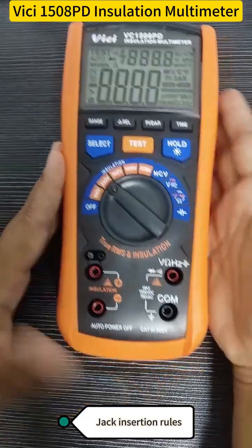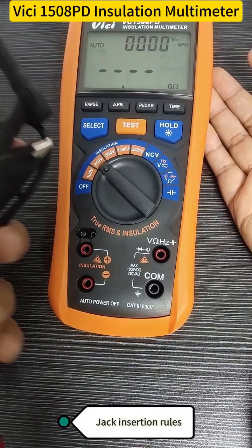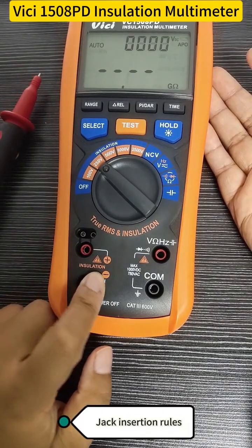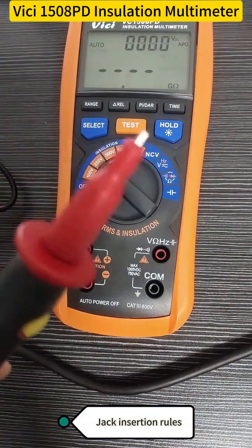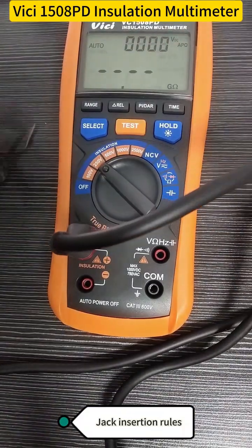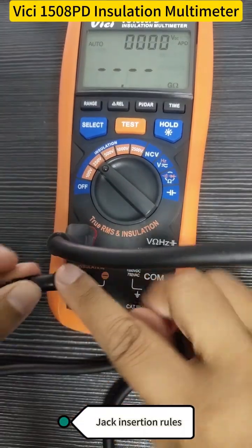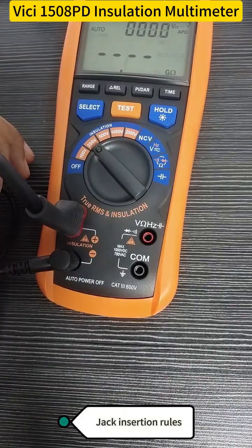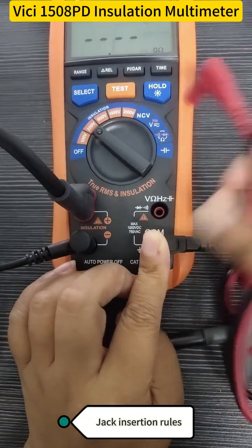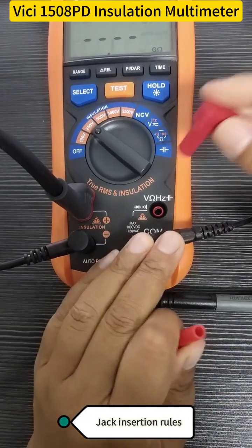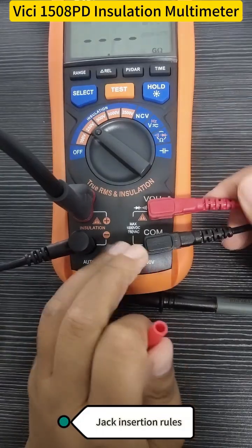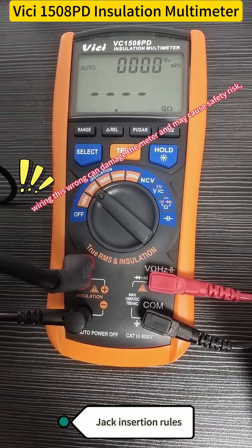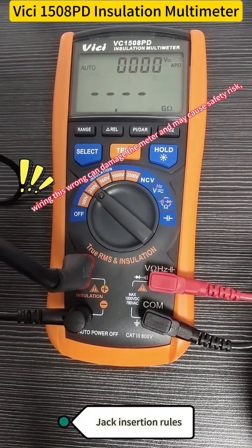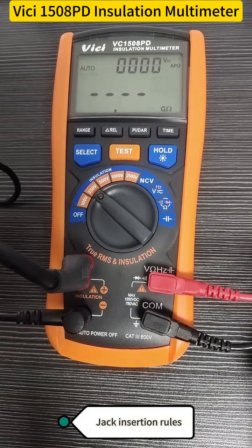Now, just keep this rule in mind. The left jacks and this pair of test leads are for the insulation test. It's marked insulation pair, and we can connect this remote test lead to the positive terminal, and this alligator clip to the negative point, like here. That's it. And for the right jacks, for the regular test leads for standard multimeter measurements, this black one goes into the far right common port, and this red one into this terminal for the voltage, frequency, resistance, and capacitance measurements. One more time on connecting the test leads, because getting this wrong can damage the meter and maybe cause safety risk, so be careful.